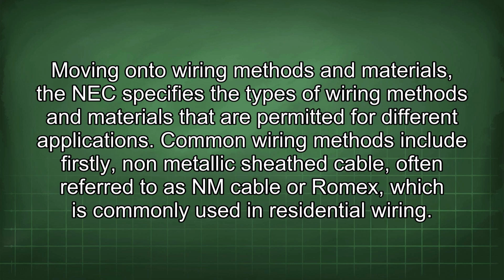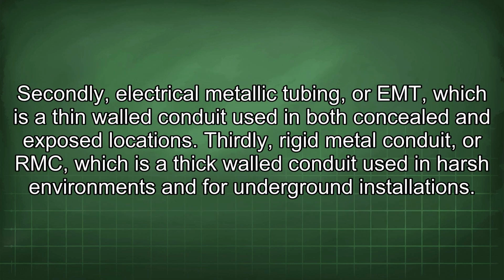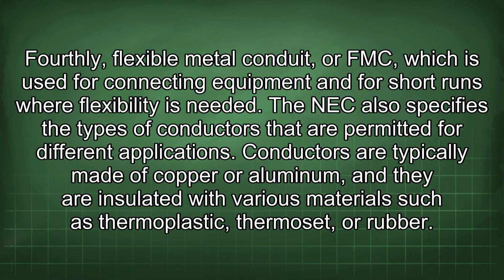Moving on to wiring methods and materials, the NEC specifies the types of wiring methods and materials that are permitted for different applications. Common wiring methods include, firstly, non-metallic sheath cable, often referred to as NM cable or Romex, which is commonly used in residential wiring. Secondly, electrical metallic tubing, or EMT, which is a thin-walled conduit used in both concealed and exposed locations. Thirdly, rigid metal conduit, or RMC, which is a thick-walled conduit used in harsh environments and for underground installations. Fourthly, flexible metal conduit, or FMC, which is used for connecting equipment and for short runs where flexibility is needed.